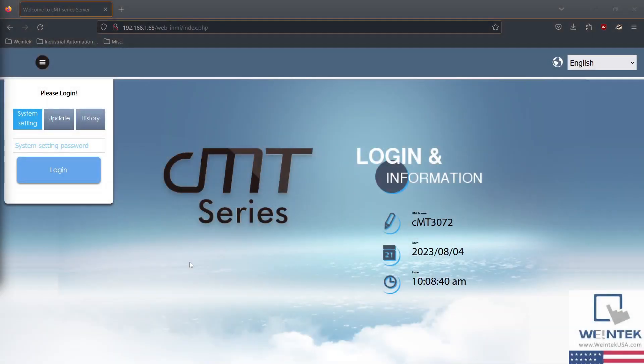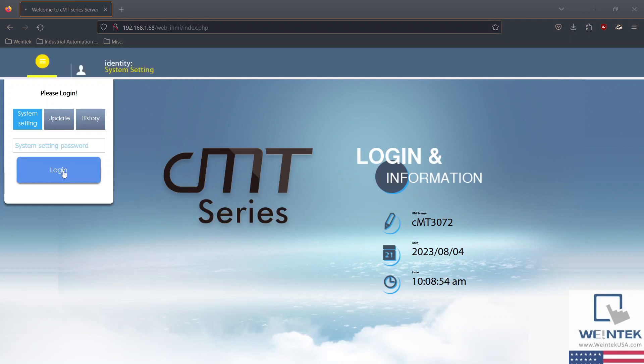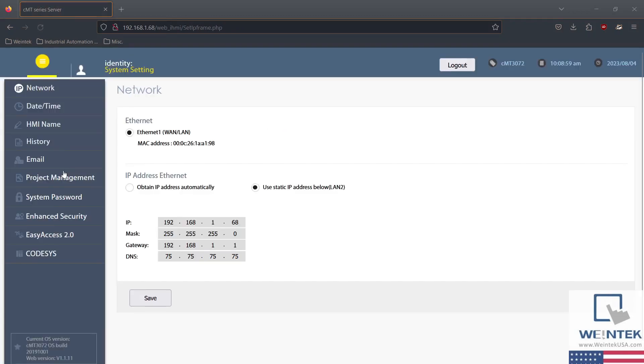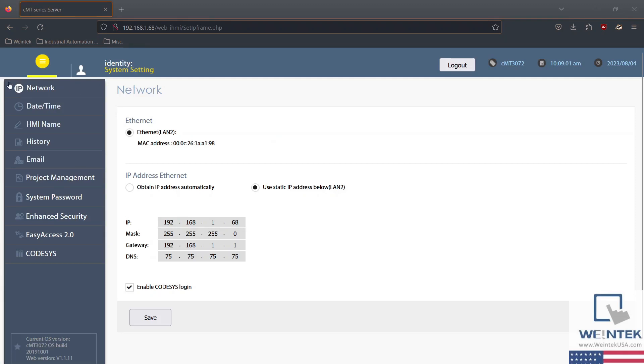Depending on the device firmware or when you purchased your HMI, the web server may appear as shown, but the network configuration process is practically the same. First, log in using your device's password — the default password is 111111. Next, within the network tab, you can statically assign your IP address or receive configuration automatically via DHCP server. Select Save when you are finished.